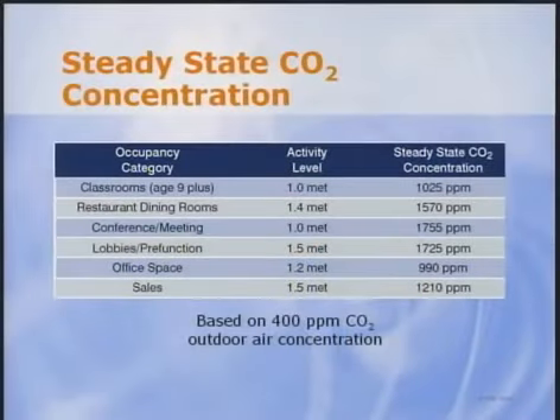This table shows the maximum CO2 concentration that can be expected in example spaces given the activity level listed, using the default occupancy density suggested in Standard 62.1 and assuming 400 ppm outdoors. Other than offices, they are higher than the 1,000 ppm that is often used as the set point for DCV under 2001 and earlier versions of Standard 62.1. This is because the CFM per person is lower under the current standard. So under the current standard, it's okay to have a reading above 1,000 ppm. Let's get into the details.